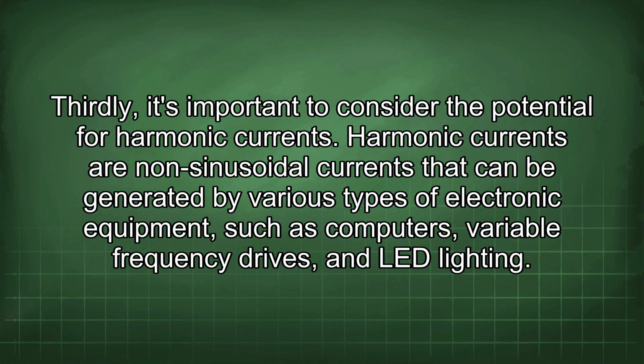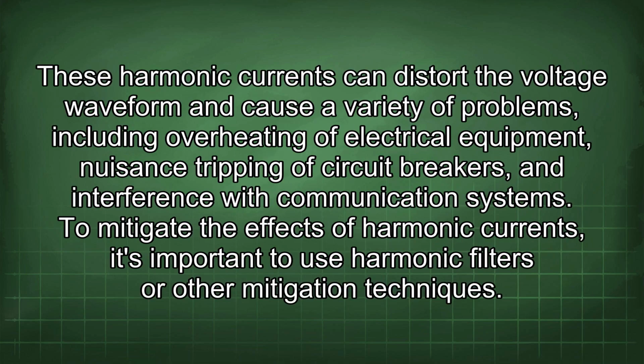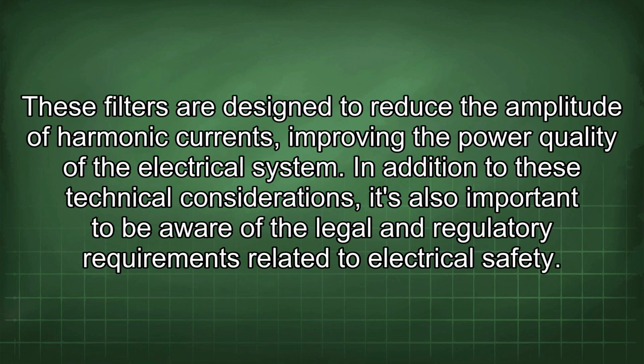Thirdly, it's important to consider the potential for harmonic currents. Harmonic currents are non-sinusoidal currents that can be generated by various types of electronic equipment, such as computers, variable frequency drives, and LED lighting. These harmonic currents can distort the voltage waveform and cause a variety of problems, including overheating of electrical equipment, nuisance tripping of circuit breakers, and interference with communication systems. To mitigate the effects of harmonic currents, it's important to use harmonic filters or other mitigation techniques. These filters are designed to reduce the amplitude of harmonic currents, improving the power quality of the electrical system.